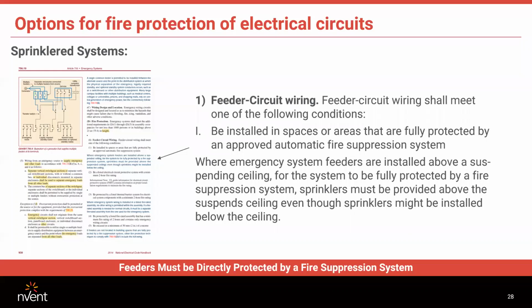One thing for emergency feeders, if the emergency feeder is directly protected by a fire suppression system, the feeder would not have to be fire rated. Now note the note right here, where emergency system feeders are installed above a suspended ceiling, for the system to be fully protected by a fire suppression system, sprinklers must be provided above the suspended ceiling, even though sprinklers might be installed below the ceiling. So basically, if you have a suspended ceiling and you have sprinkler heads coming out of the ceiling, and you have an emergency feeder running above that ceiling, unless there are sprinkler heads up there, which there's not going to be more than likely, that feeder is going to have to be fire rated. The feeder must be protected by the sprinkler system for the entire run.